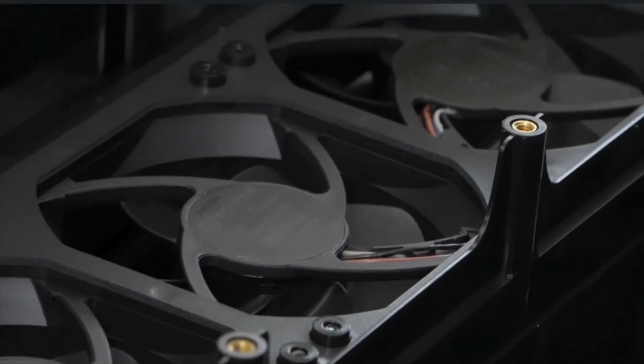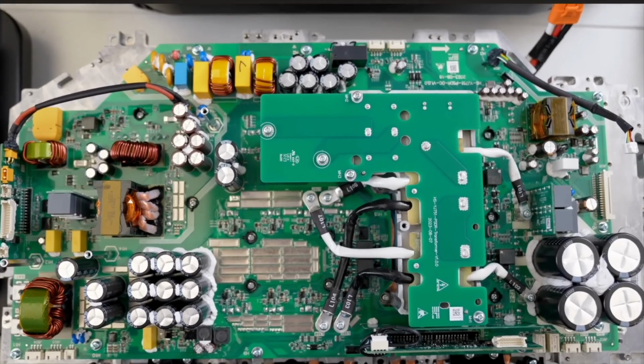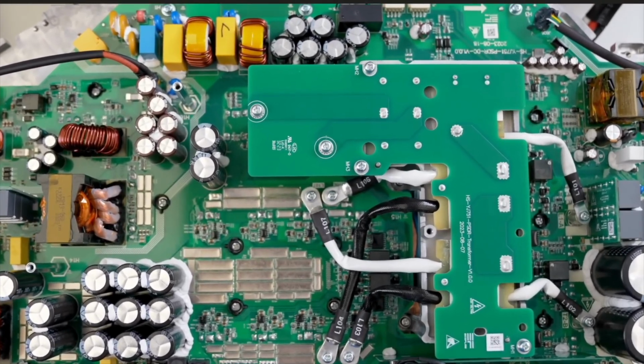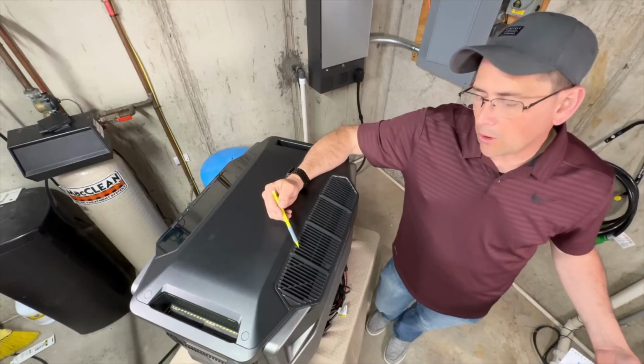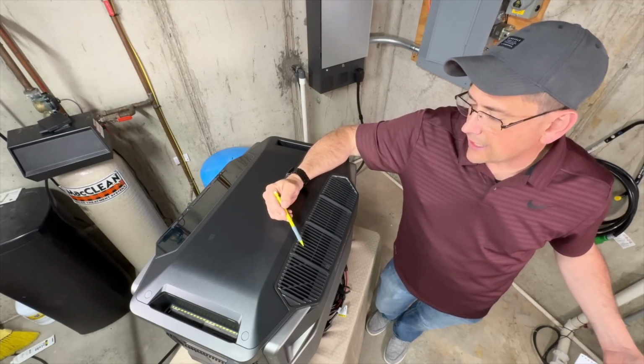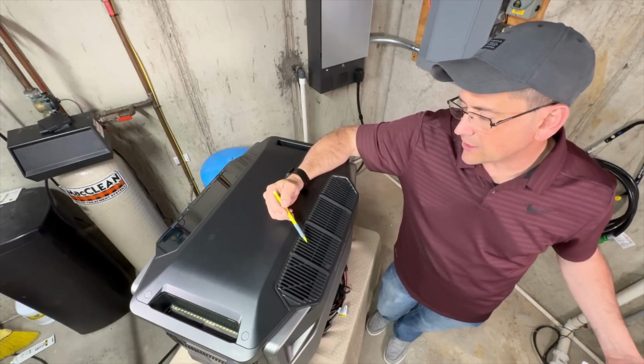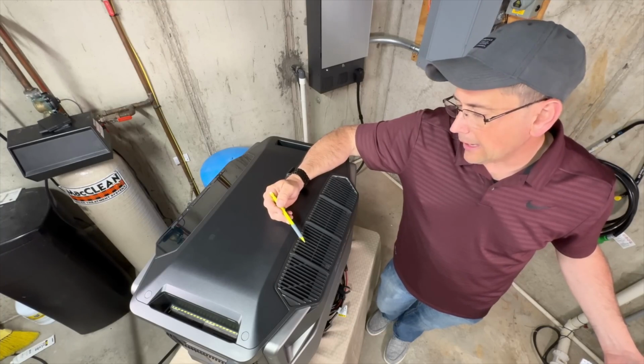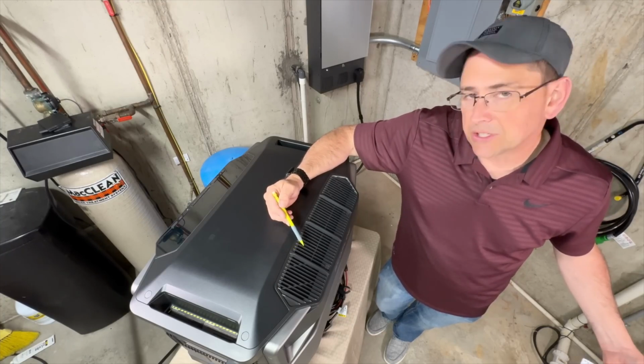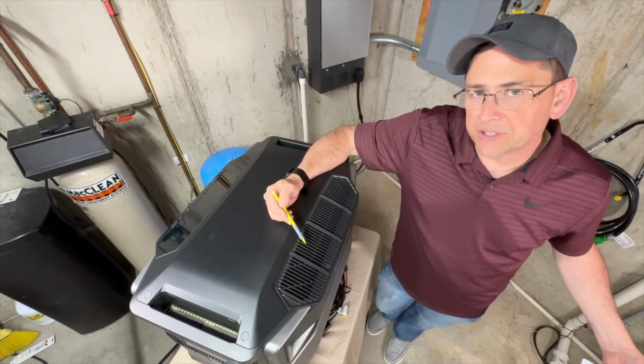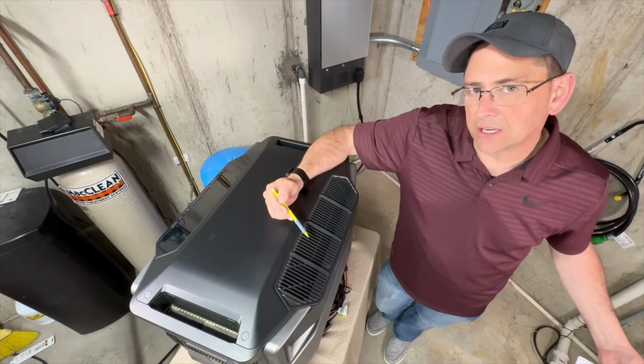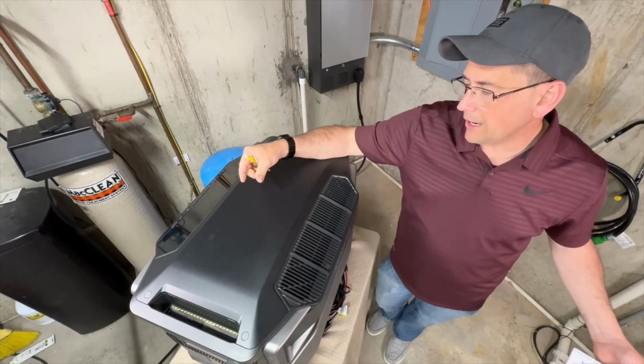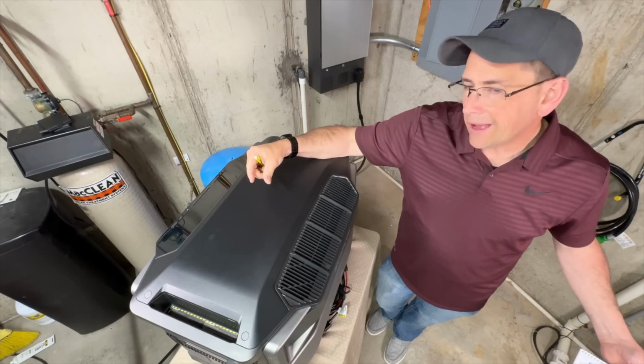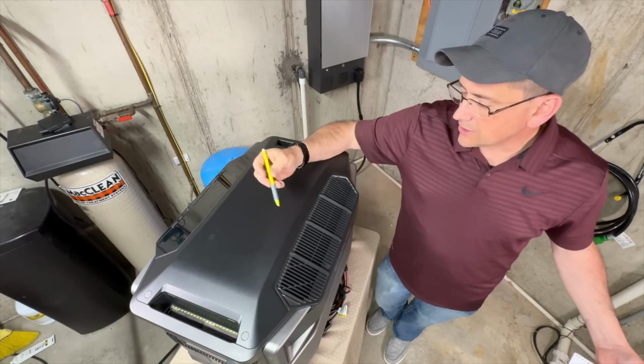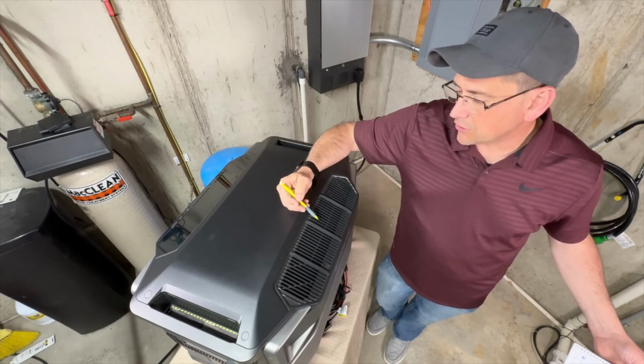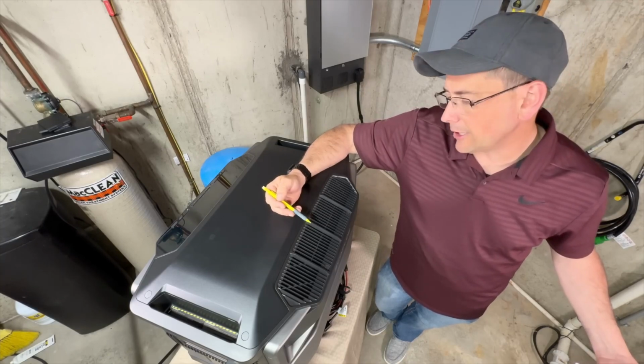This unit is rated for up to 2000 watts, whether charging or discharging, without even needing the fans to run. In my next video I'll do testing that shows exactly how much noise this machine puts out, but I'll let the cat out of the bag now: running it at about 4600 watts nonstop for over 15 minutes, then checking with an actual SPL meter held not even this far from the fans, I got about 41 dB. So this thing can be kept near a bedroom without worrying about keeping somebody awake at night.